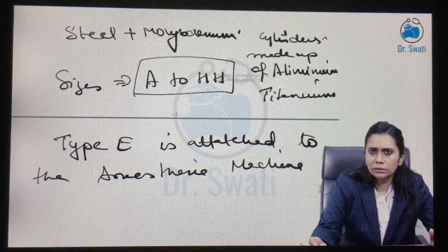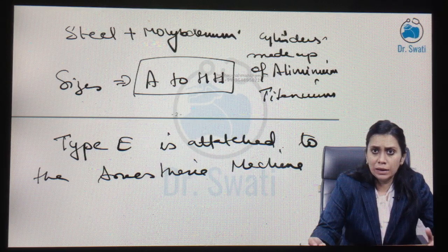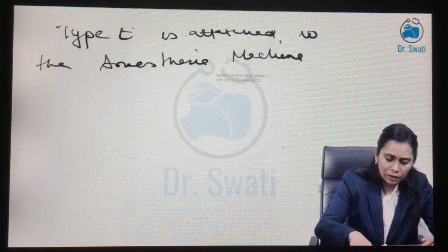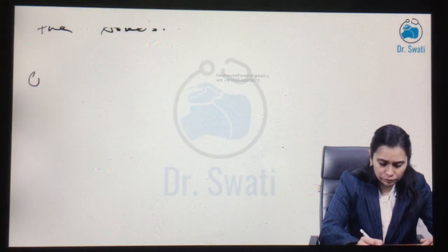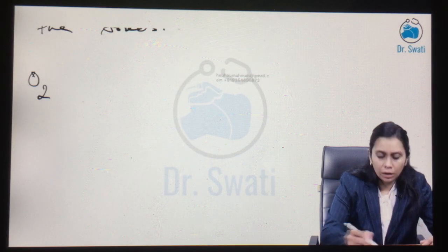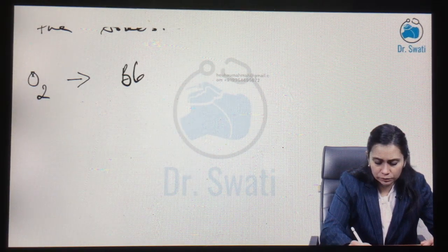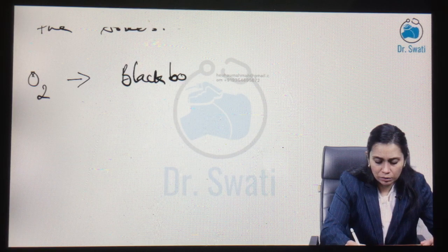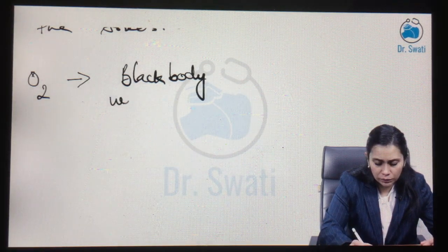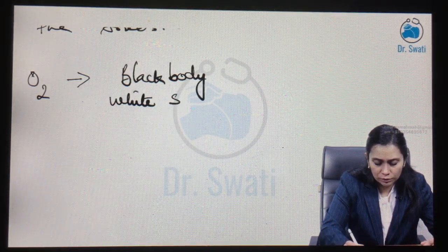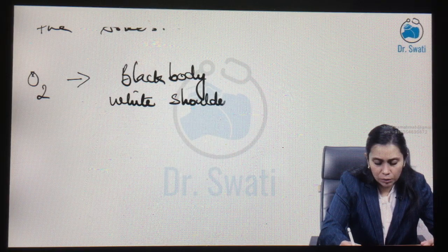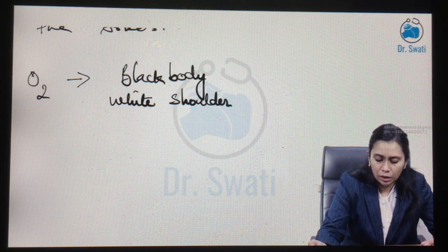Now let us discuss few gas cylinders, their color coding, their pin indexes, and some clinical questions asked on them. Okay, so let us start with oxygen. Well, oxygen cylinder, you all know, has black body, white shoulder, right?